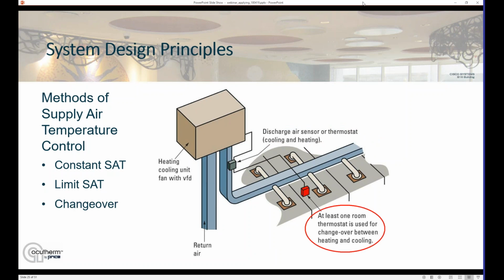For the third point, the means of changeover, at a minimum, we need a temperature sensor in one of the rooms. We don't like to recommend the return to the unit because that's an average of all the rooms, and you miss your peaks, your highs and your lows if you're sitting in the average. Not to say you can't put a sensor in the return from one of the rooms, though, because that's, again, not an average temperature. That's the one room. And it also doesn't have to be as simple as a single sensor. If you want, you can use multiple sensors and use a voting sequence on when to switch between the heating and cooling modes. If you start to look at some of our electric diffusers, which can be tied in over a BACnet network, that can be a great way to bring in the temperature from multiple rooms, run a voting sequence, and decide when to switch on the heating and cooling based on that data.